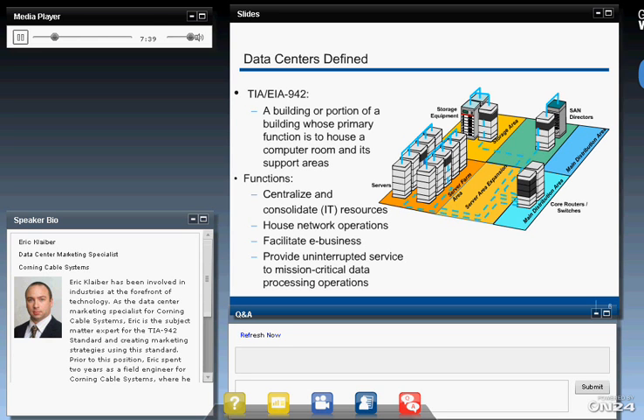Case in point, with Sandy, the data center's backup generators were on the upper floors, so they weren't harmed by water, but the pumps that feed diesel to those generators were in the basement, and they flooded. So when the power went out, there was no way to get diesel up to the generators. They were actually using 5-gallon buckets, one in each hand, going up 14 floors of stairs in a bucket brigade for these mission-critical functions.